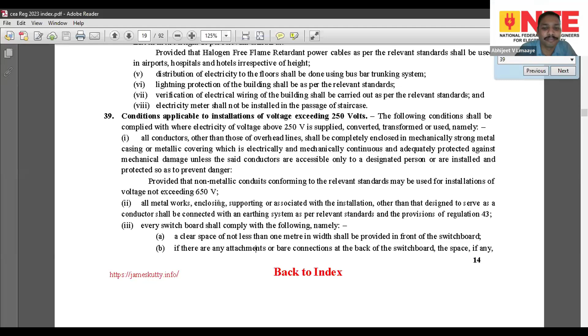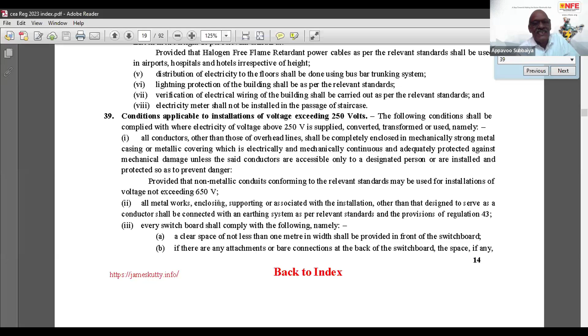This appears simple, but the practical problem is people do not plan initially, and they all want the electrical panels to fit in the space available. It's not planned ahead; they come to the final stage and put it wherever space is available, and finally it gets rejected for lack of front or rear clearance. So this seems simple, but it gives a major hurdle while affecting supply, and in some cases the supply was rejected, then an additional building was constructed just to accommodate the main panel. This is important for consumers to consider while planning.